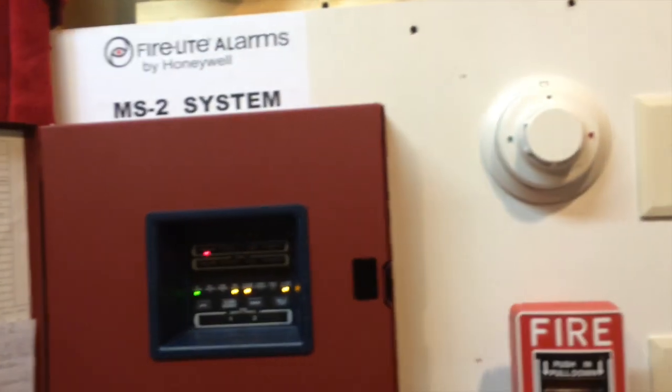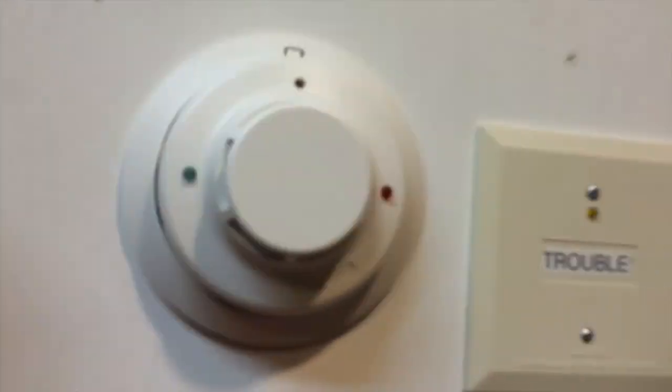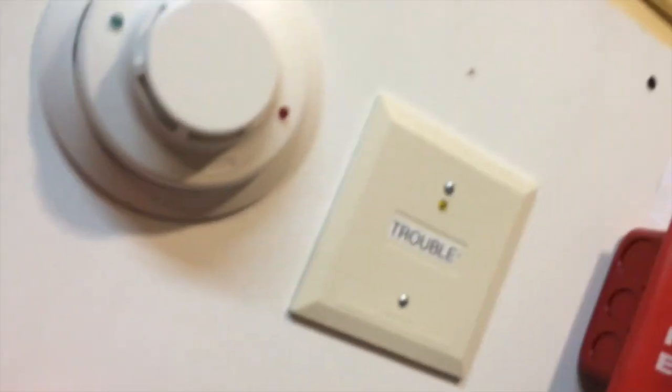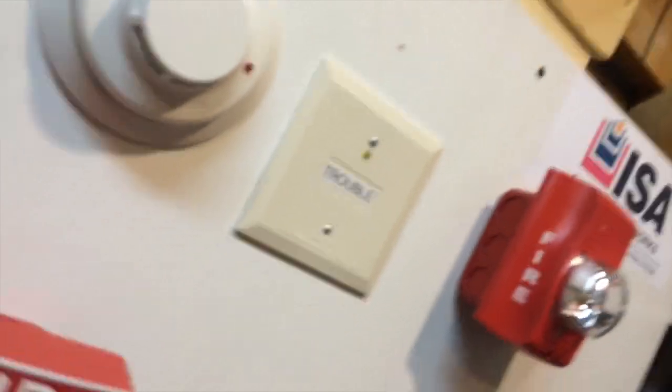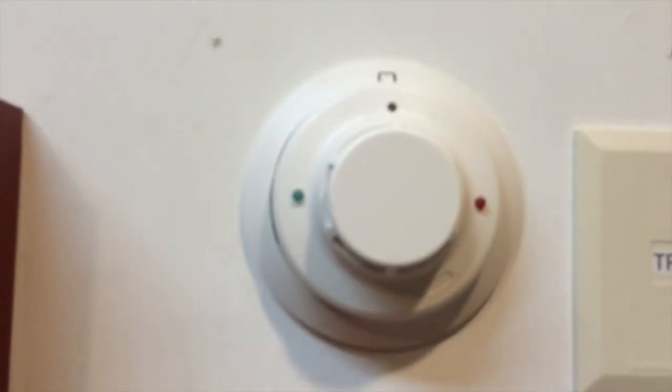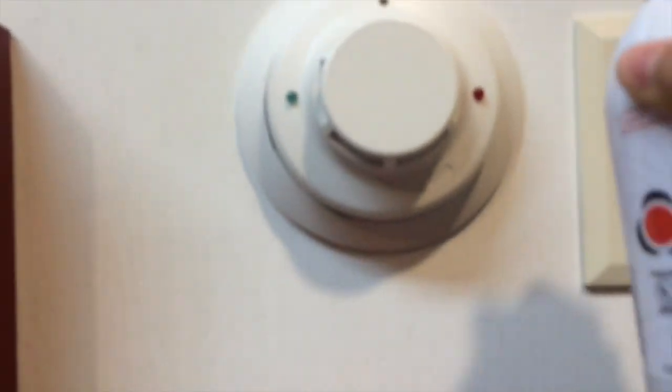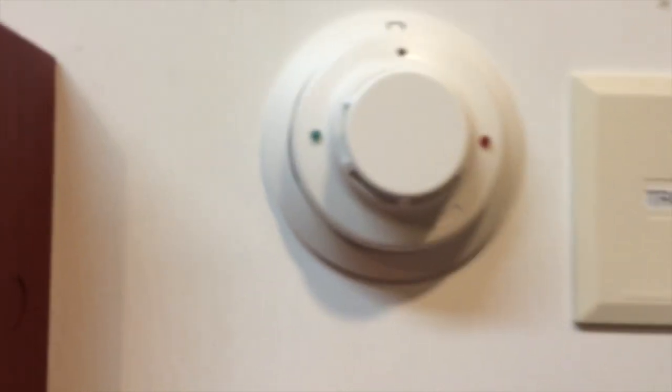So, okay, so now Zone 1 is disabled, as it's saying. It's saying Troubled. And so, if I go ahead and spray some of that solo stuff in it again, it won't go off. I'll quickly demonstrate that, just for the sake of it. So, it's not going to go off since it's disabled. So, that's one of the good things about panels that you can disable Zone, because if you're doing a smoke test. I just blew it out.